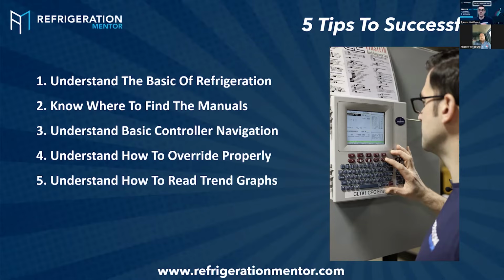But the one thing with any electronic is it needs to read the correct information. So if it says the produce case is running at 38 degrees, but you go down there and they're losing product because it's too cold, while the sensor's reading 38 degrees - well, the computer is just doing what it's told. So it's very important those inputs on that board are exactly reading what they're supposed to. You have to verify that.